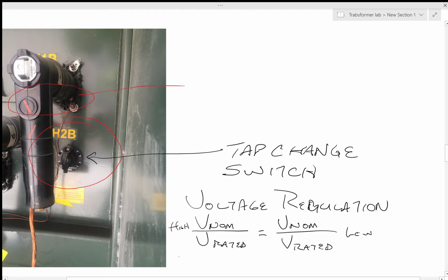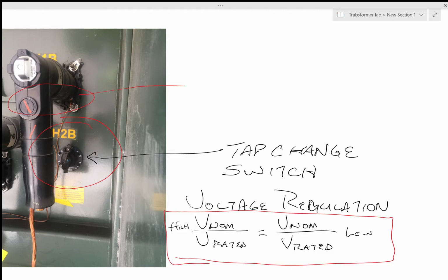And here is the formula that they gave you on that transformer video. You had a high side, the nominal voltage, or what the actual voltage is. Some people call it nominal. It can also be the actual value of the voltage. And then the rated voltage is the rated voltage of the transformer, called the transformer nameplate. And we'll get to the nameplate here in just a second. It's on the low side of the transformer.